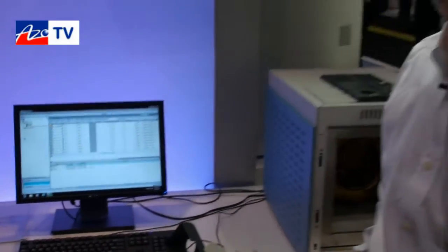That means somebody could be sitting in their office gathering all the data while the machine is in another laboratory. Exactly — in a quality production laboratory, you might have a number of instruments remotely controlled by a chemist in a different room or different location connected by ethernet. The modularity of the design also means that if you don't have a big budget to start with, you can buy a fairly simple machine and then upgrade — in principle, buy the mainframe with no injectors, no detectors, and then buy the modules in a second step.